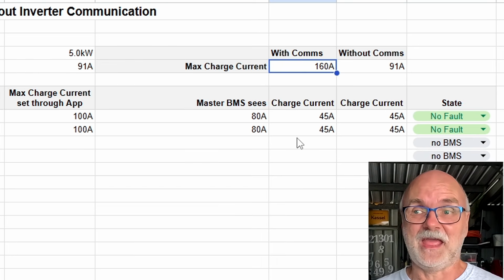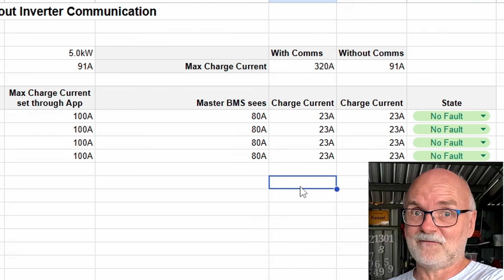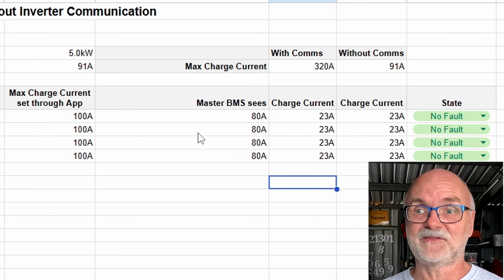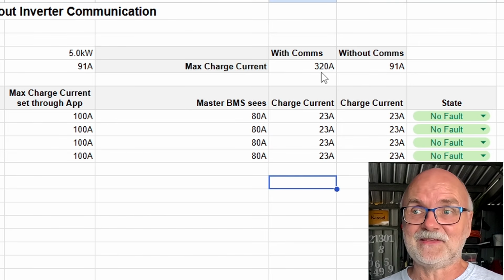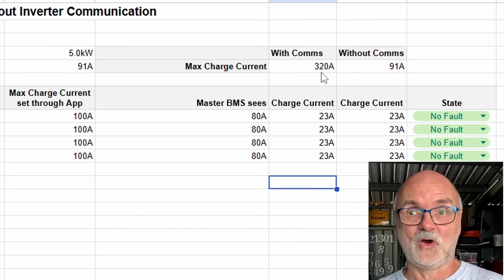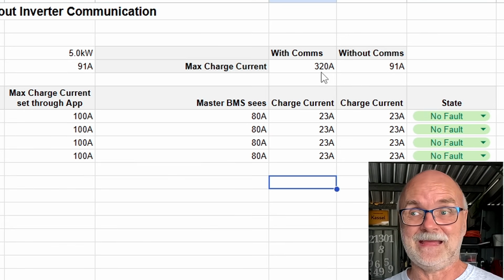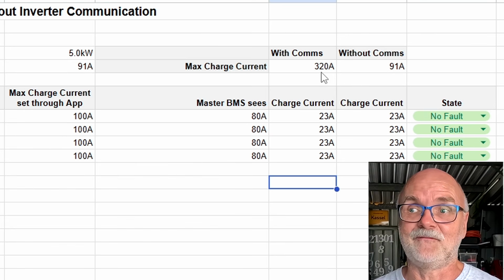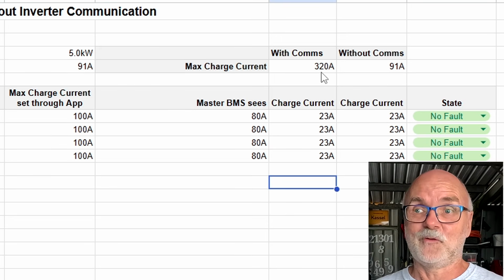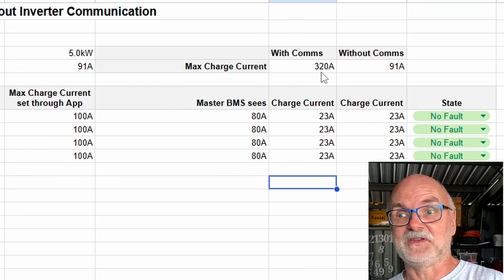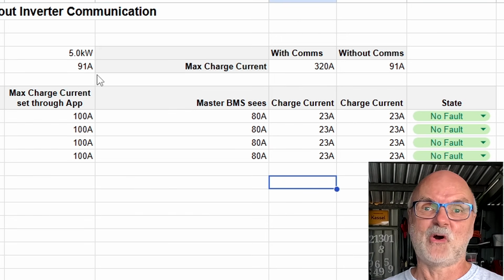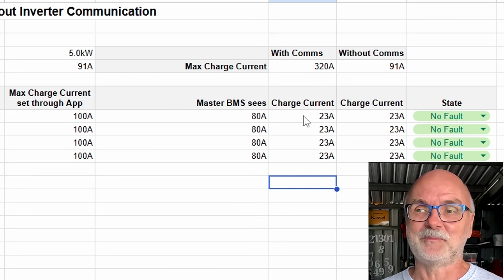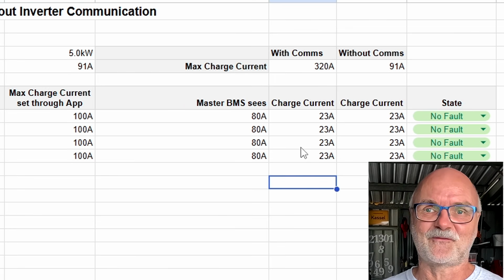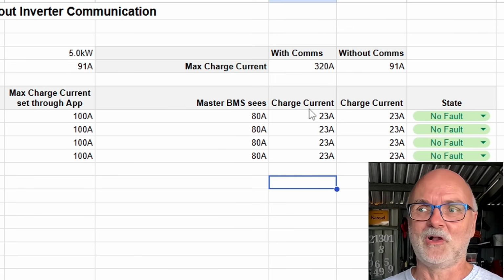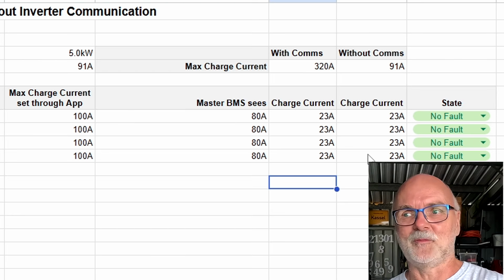So no issue there. Let's have a look at the system we have tested right now: 4 batteries, each of them set at 100 amps. We can see here the CCL, what is reported to the inverter, requested 320 amps. Yeah, that's what we have seen in the Victron system all the time. So we tell the inverter, charge me with 320 amps. Your solar system can do only 91 amps. That would mean 23 amps in each of these 4 batteries. No problem at all, with communication or without communication.